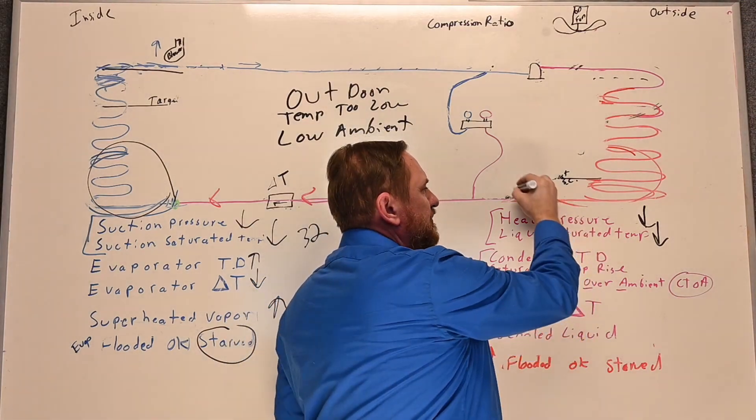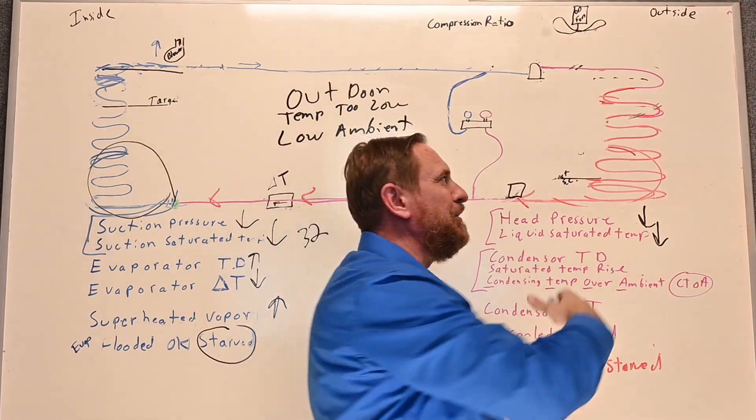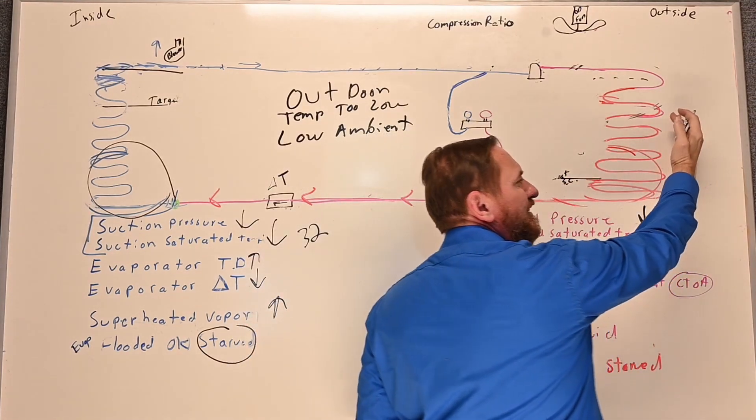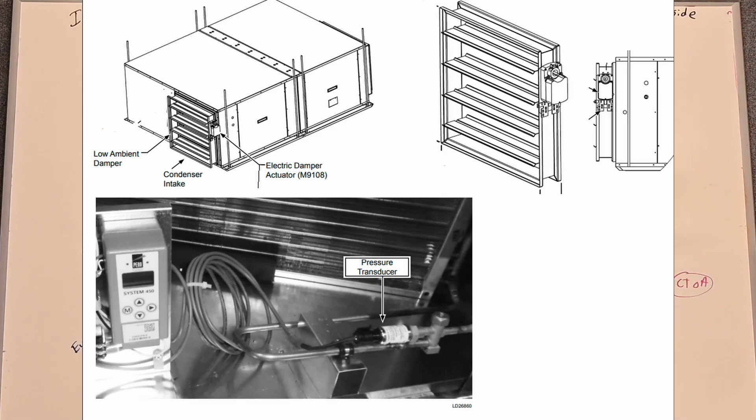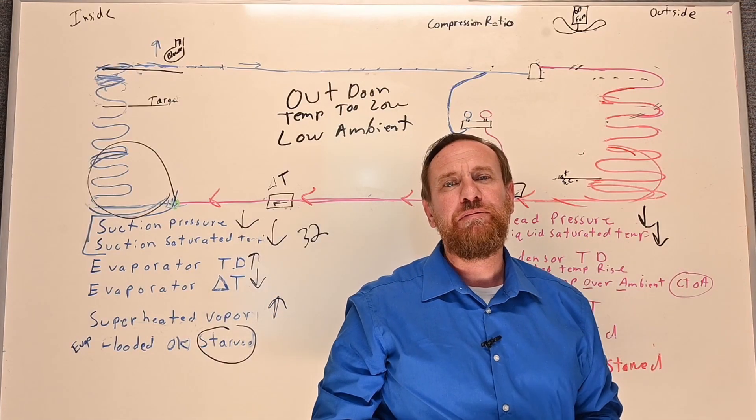Another method we use is we can use a pressure switch right here in this line, and we can use that pressure switch to control dampers. We control the amount of air going to the condensing unit by controlling dampers, opening and closing, controlling how much air goes. That's really impractical for residential systems, but it is a way of controlling head pressure.